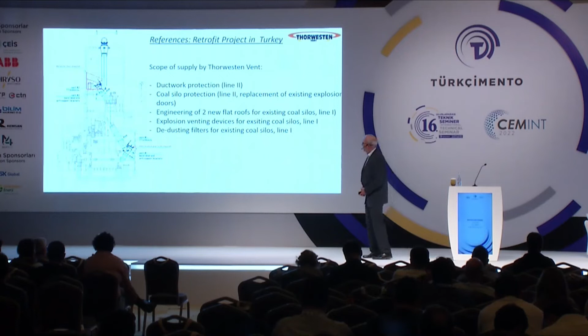Last but not least, I have to mention definitely also the substitution of fossil fuels by alternative fuels. One major fuel that is currently very often used is dried sewage sludge. And dried sewage sludge can create dust explosions if the so-called dry substance content is above 85%. If the moisture content is higher, then the users and owners have to fear gas explosions due to the emission of CH4. You see it here. That happened already. Therefore, the composition of the dried sewage sludge is really important to know.